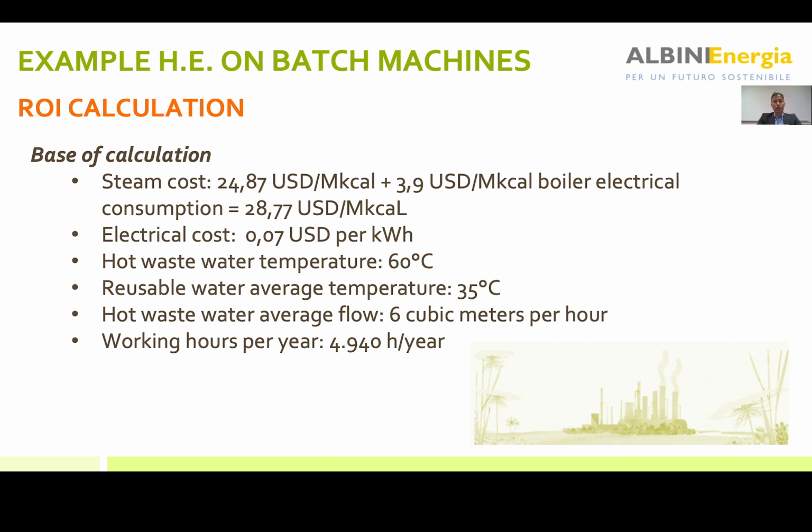The electrical cost we have considered in our return of investment calculation was 7 US dollar cent per kilowatt hour. And the wastewater temperature at the origin for the first reading was 60 degrees, and the reusable water average temperature was 35 degrees. Finally, the flow was around 6 cubic meter per hour.